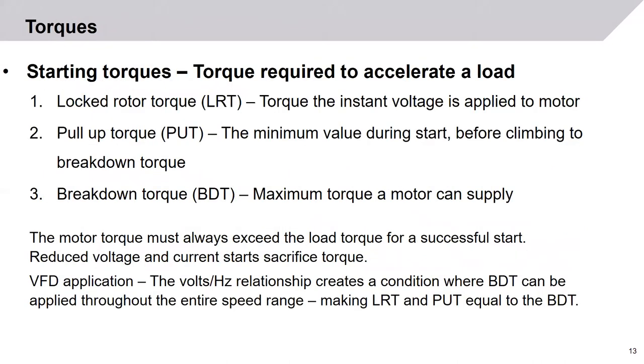Now there are also starting torques — the torque required to accelerate the load. The two specifically to be concerned with are lock rotor torque, which is the torque the instant voltage is applied to a motor, and pull-up torque, which is a minimum value during the start of the motor before it climbs up to breakdown torque. Breakdown torque is the maximum torque a motor can supply running close to its rated speed. The motor torque must always exceed the load torque for a successful start. If you reduce voltage or reduce current, it will sacrifice torque.